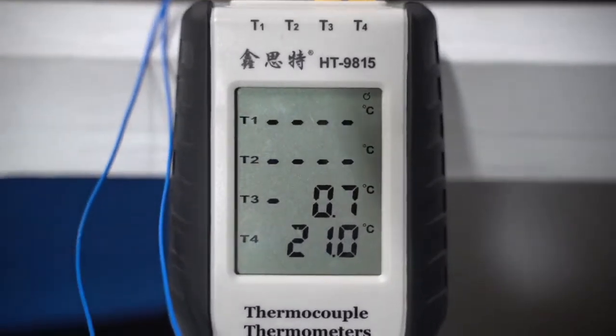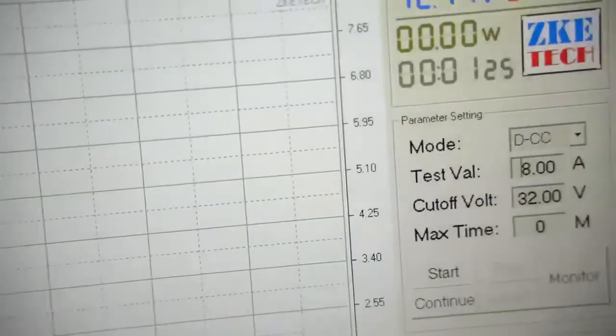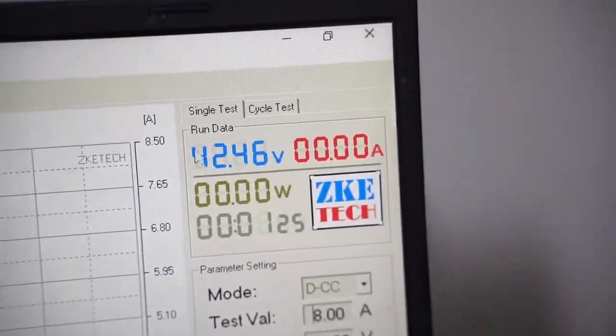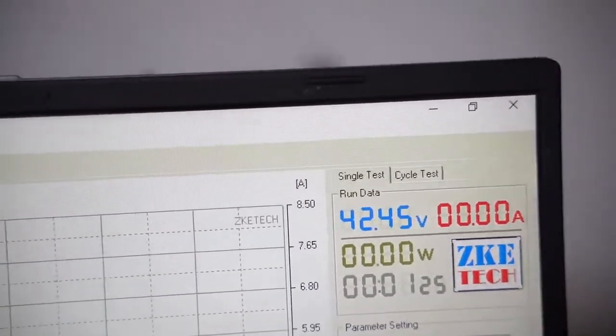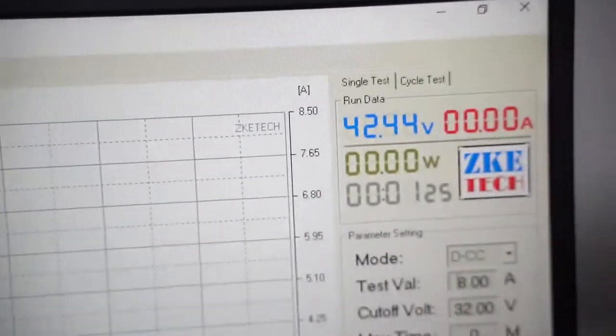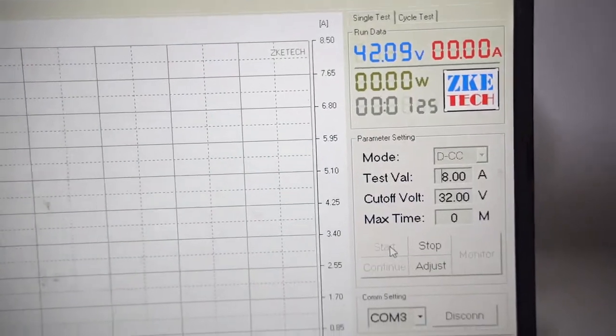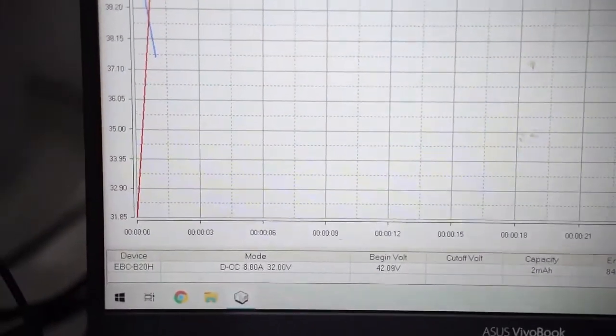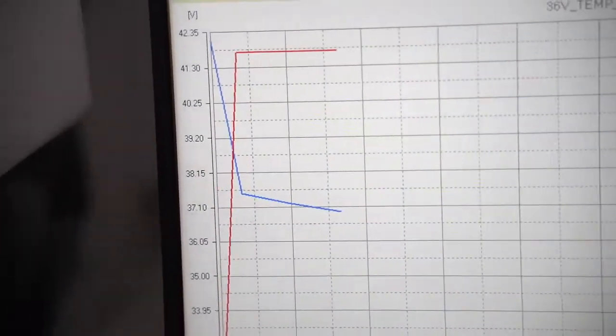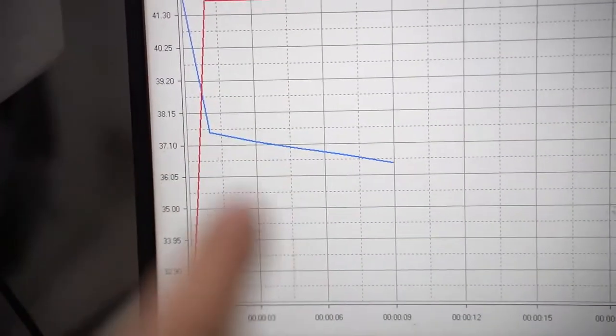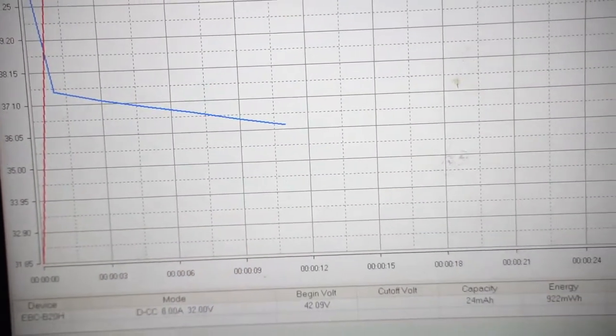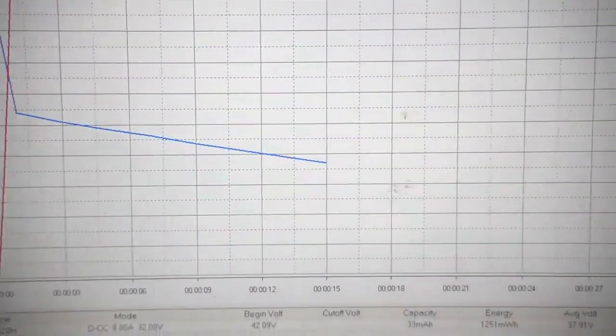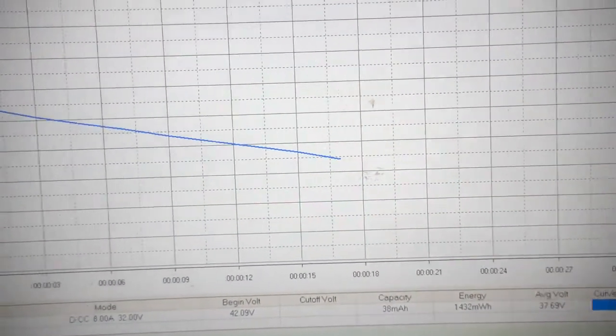Alright, so what we're going to do is run the discharge. Just for record keeping, it's at 42.46 volts. That's normal because we are also running the heating element off the same battery that we are discharging. Okay, so we're going to start it. There you go. Hear the fan running. Right. See the curve shooting down. So that's going to be a very quick test. It won't take long before it actually hits the lower cutoff voltage.